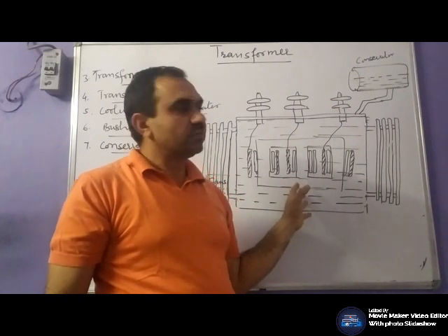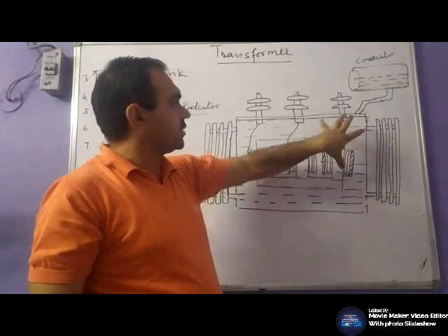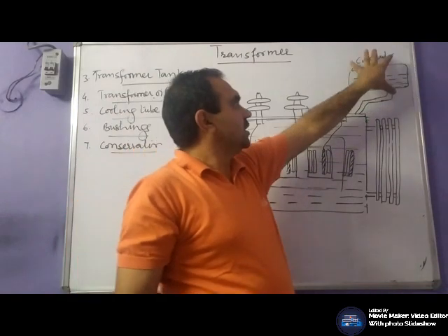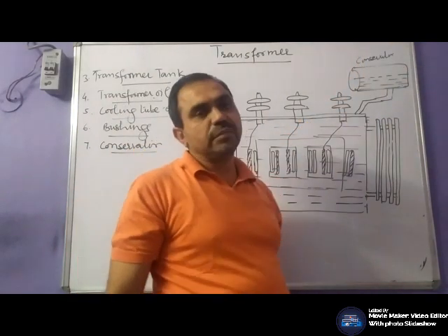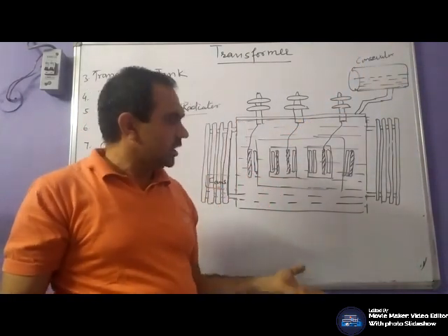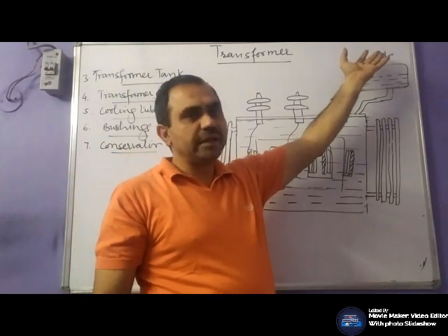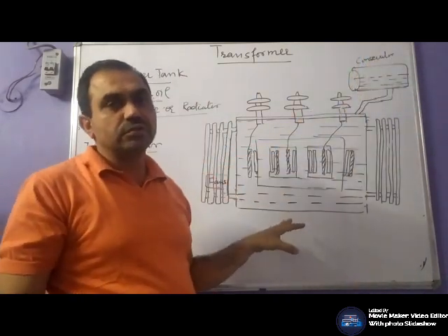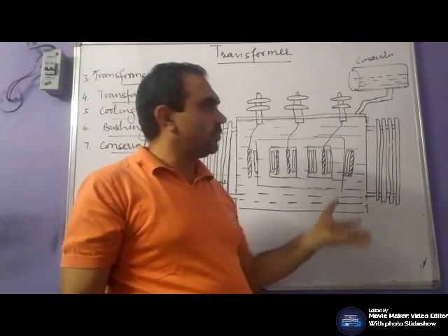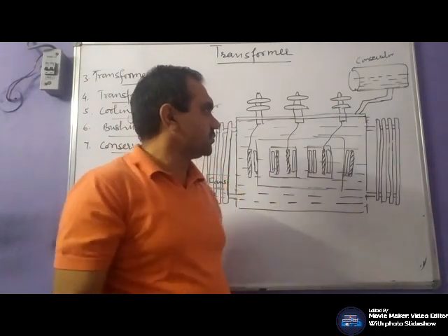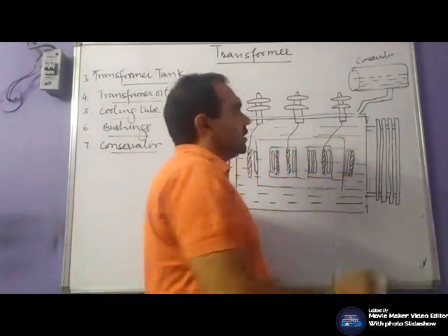So to maintain the required oil, this conservator is used. During heat up the oil expands, and during cooling down it supplies the oil back to the transformer.